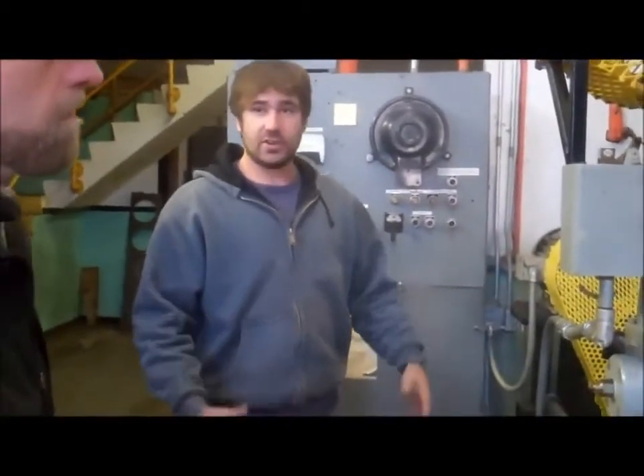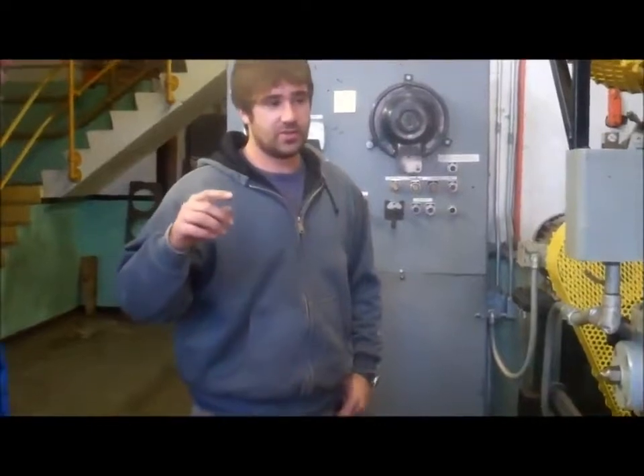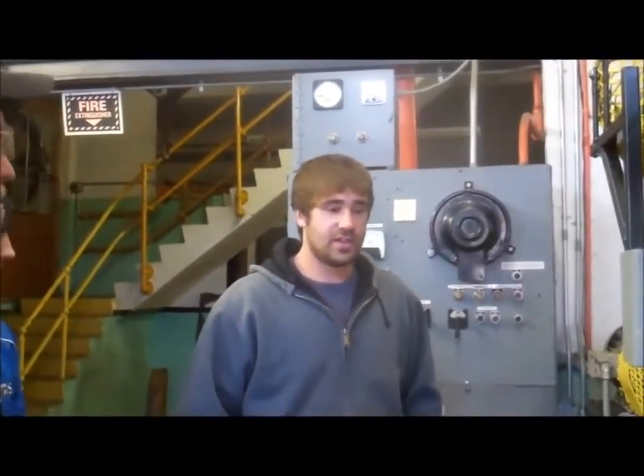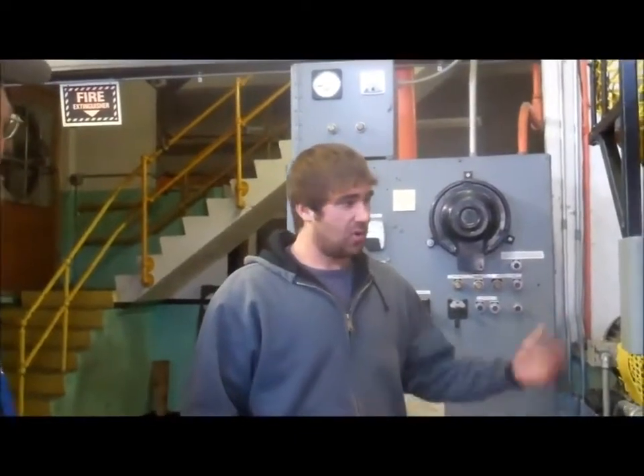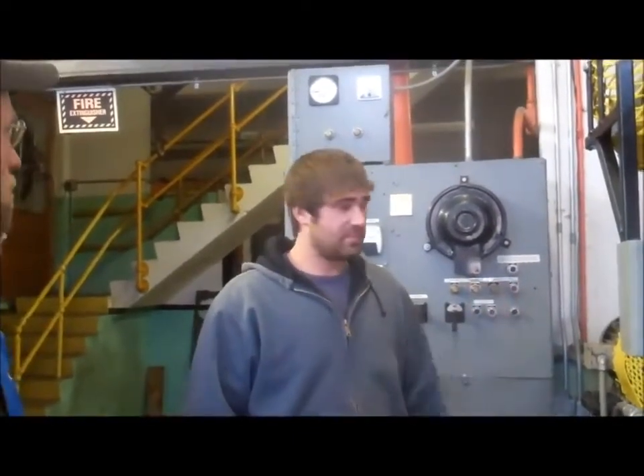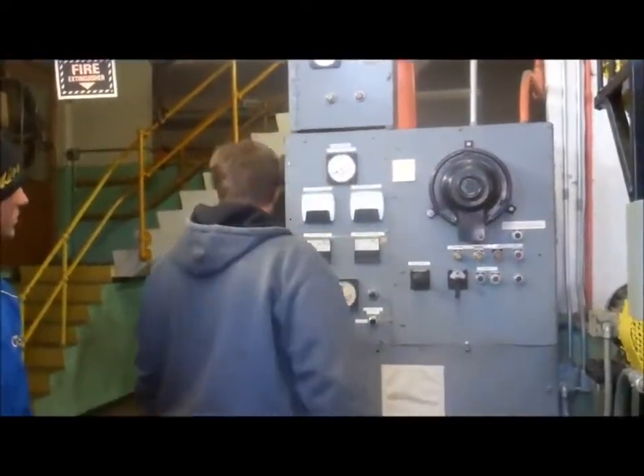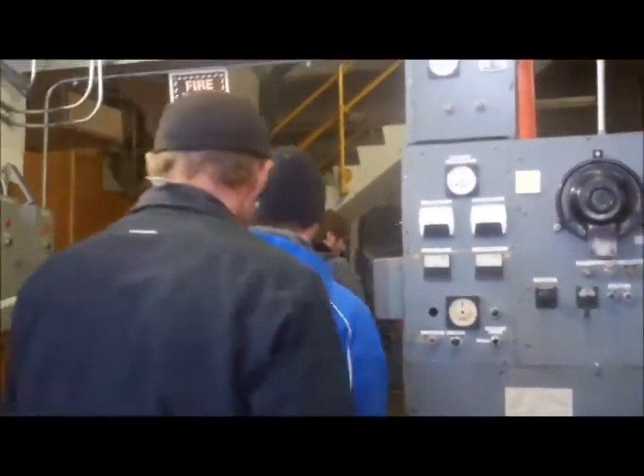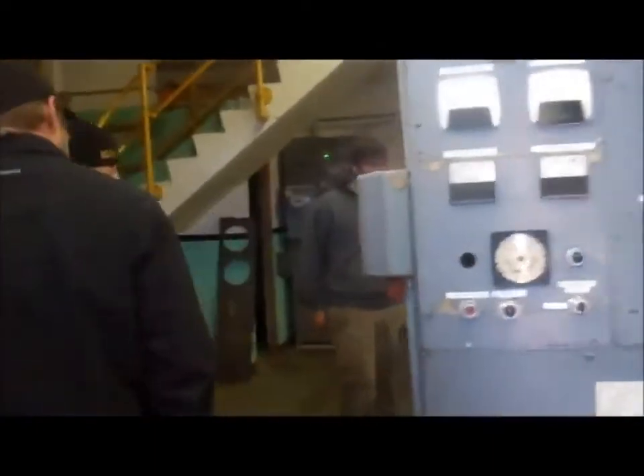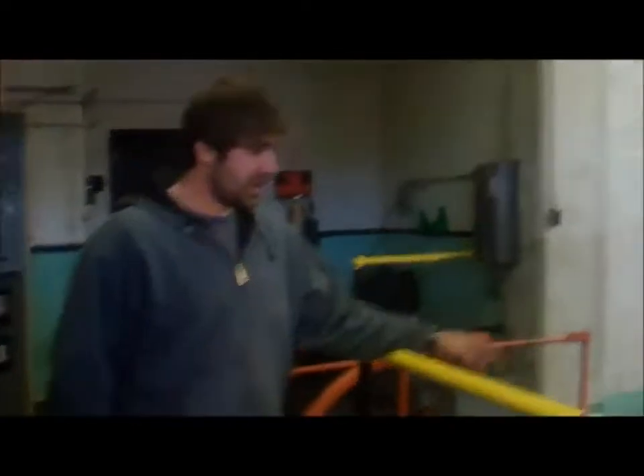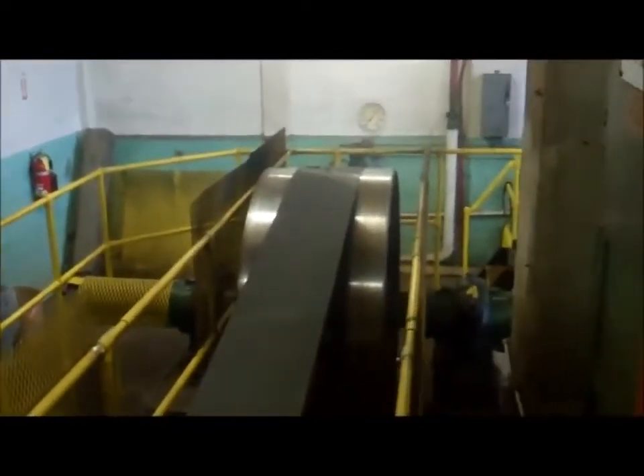Now, because we have synchronous machines, the generator is always spinning at a constant RPM because it's locked in phase with the grid. So it's a 60 hertz system is what we run in the United States, and that will only let this machine run 600 RPM. And belt driven over here. We have the big sheave spins 200 RPM, the small one spins 600. And this is the only belt driven machine, but you can see how it's been modified.